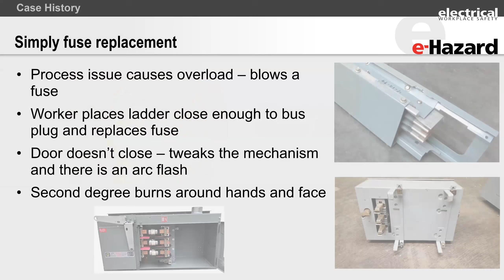What were the gaps? The gaps here were obviously ergonomics, the angle of approach and visibility. Article 130.8 speaks about blind reaching. It also talks about the person failing to visually check what they were doing, one-handed testing. Why is that wrong? You need two hands to check both phase and line voltages.